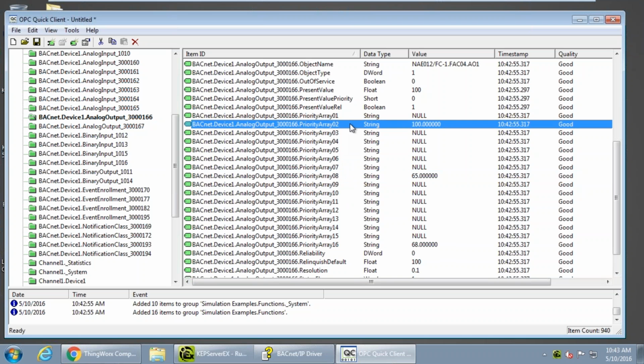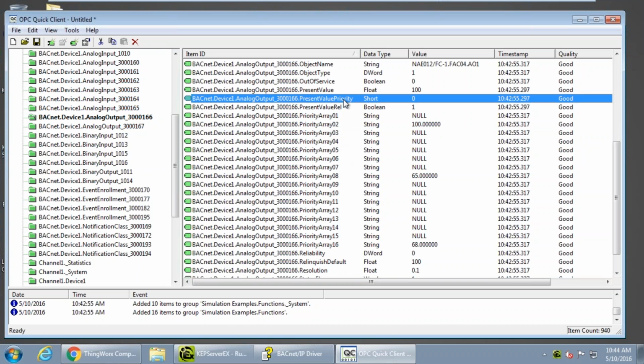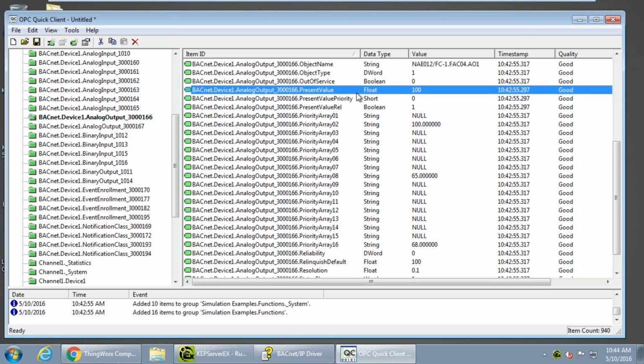If you get into an emergency situation where you need to absolutely shut that blower off because of a fire or something, you can hop to a higher priority with a different value set for those emergency scenarios. This might be hard to follow if you're not familiar with BACnet, but hopefully those who are understand how you can command the present value using the priority array.